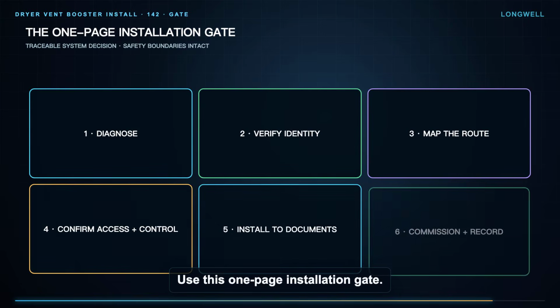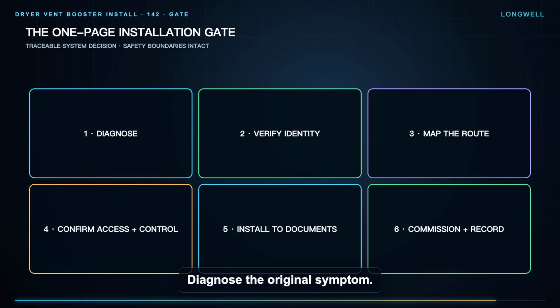Use this one-page installation gate. Diagnose the original symptom. Verify the exact dryer, exact ventilator, physical label, current certification, and local permission. Map the complete route. Confirm placement, support, control, electrical work, service access, and maintenance. Install only to the controlling instructions. Then commission the entire path and document the result. A premium dryer vent booster installation is not the fastest route to a spinning fan, it is a traceable system decision with every safety boundary still intact.